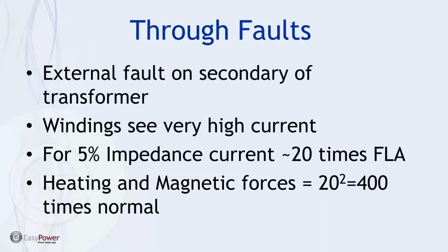Now, a through fault is basically defined as an external fault on the secondary of the transformer. And it's just a fact, based upon the turns ratio, that the windings see very high current when we have an external fault. For instance, for a 5% impedance transformer, the current can be as high as 20 times the full load current.